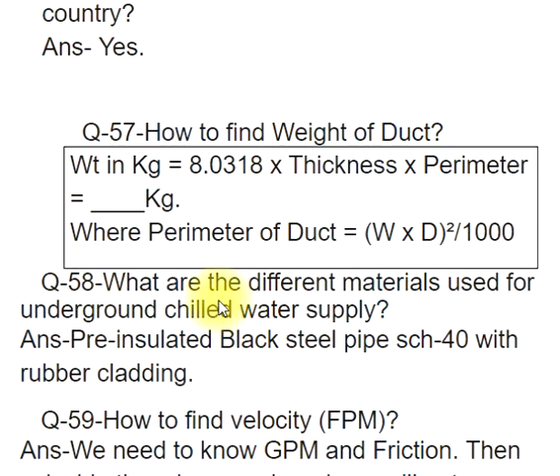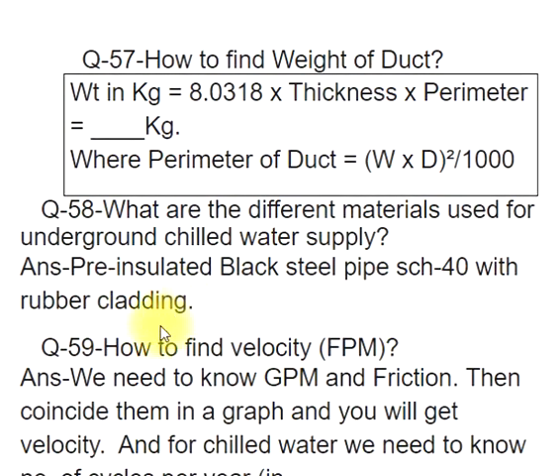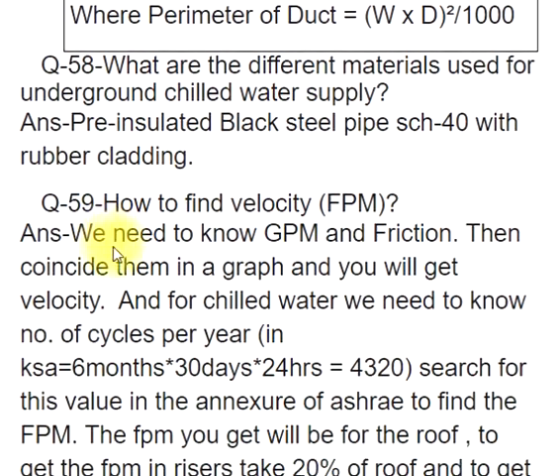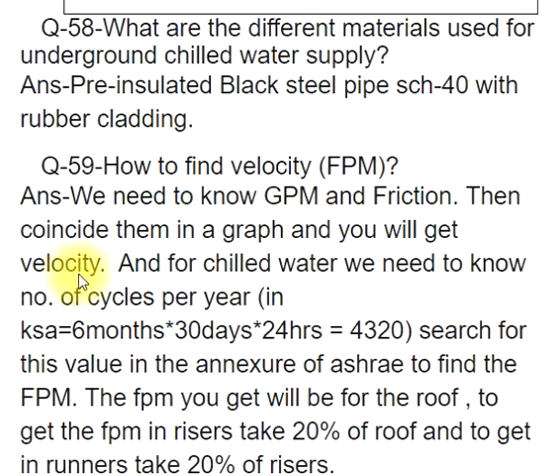Q58: What are the different materials used for underground chilled water supply? ANS: Pre-insulated black steel pipe SCH-40 with rubber cladding. Q59: How to find velocity in FPM? ANS: We need to know GPM and friction, then coincide them on a graph to get velocity.